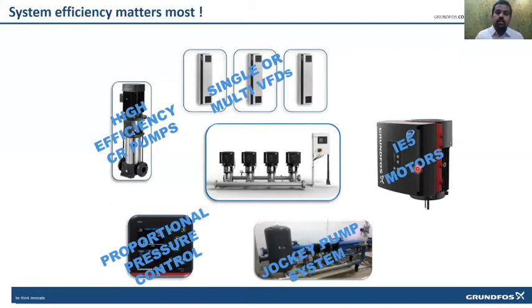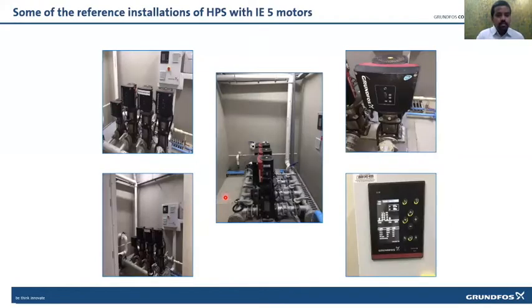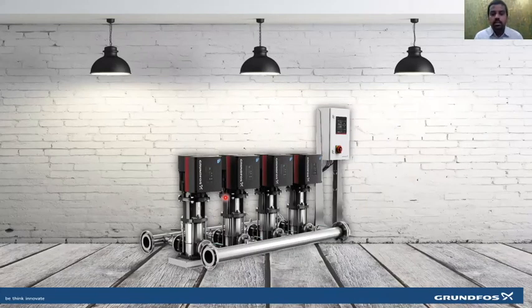So to have a better system, with lower specific energy consumption, we should have IE5 motors, jockey pump, proportional pressure, and if you have all of these with VFD, that will give more savings, of course, for handling the variable load demand. So that's it from my end. We have supplied this system for almost the last 2 years. We have sold more than 300-400 systems across India with IE5 motors, jockey pump and proportional pressure, and we definitely see energy improvement in the system behavior compared to a conventional IE3 based external drive system. So thank you, that's it from my end. If you have any queries on this specifically, please put them to me so that I can reply as relevant. Thank you so much.